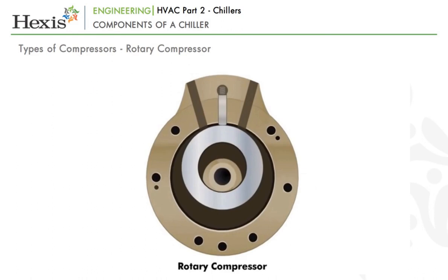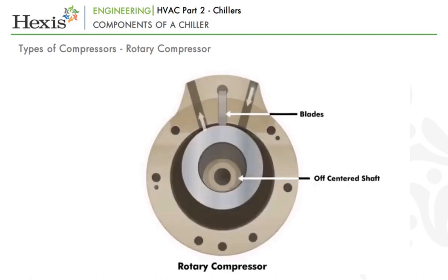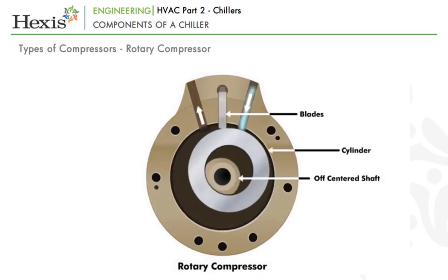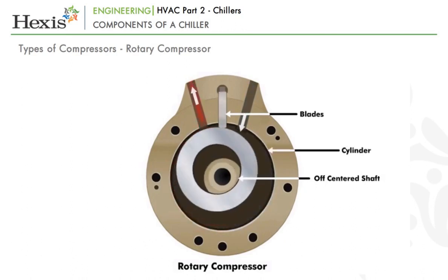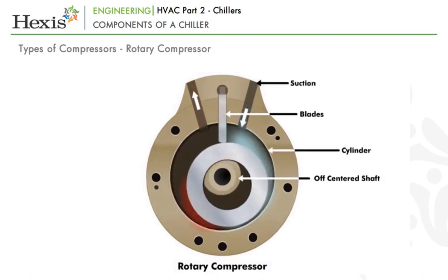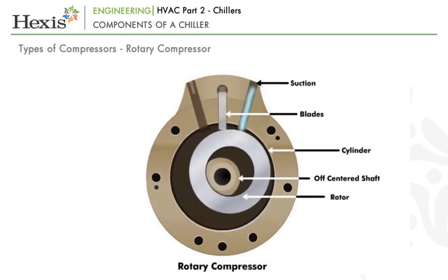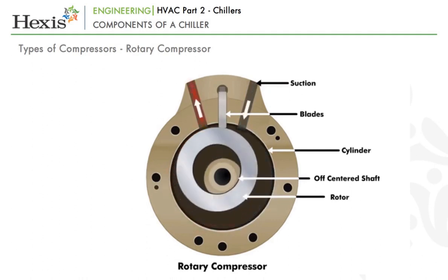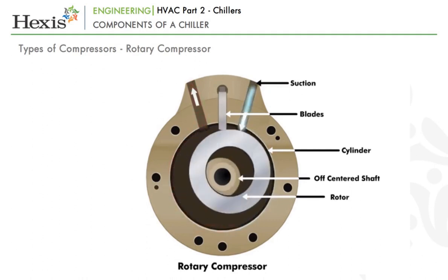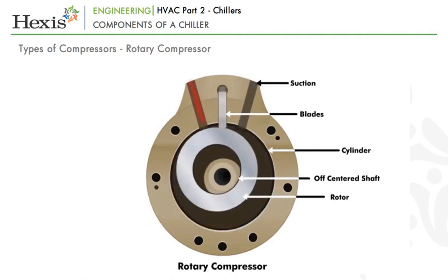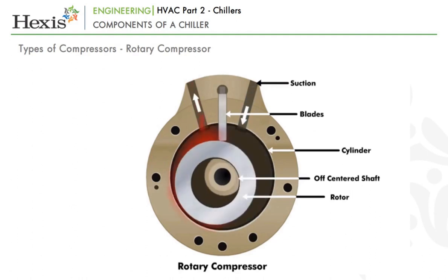The third type is the rotary compressor, which has an off-centered shaft with blades moving at high speed inside a cylinder. Gas is drawn in at the suction end, and as the rotor moves, the trapped gas is compressed by the reducing volume due to the eccentric movement of the shaft.